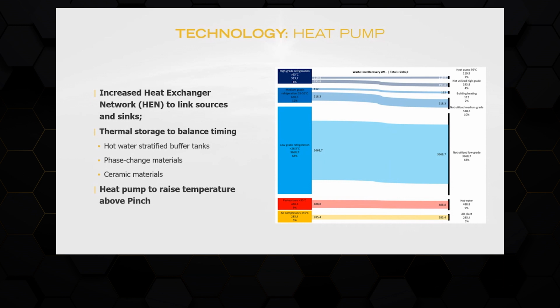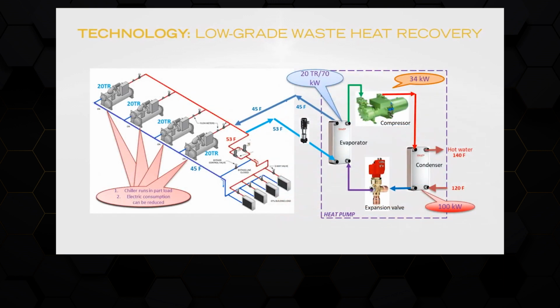So for applications like these, we designed a heat pump. Very quickly, I would like to take you through one application of a heat pump. In this case, the heat pump extracts heat from chilled water returned from the plant, so it cools the chilled water before it goes to the chiller for further cooling to the required supply temperature. So what we do is we put in a heat exchanger, technically called an evaporator, that cools or pre-cools the chilled water return and heats the refrigerant before it goes to the compressor.